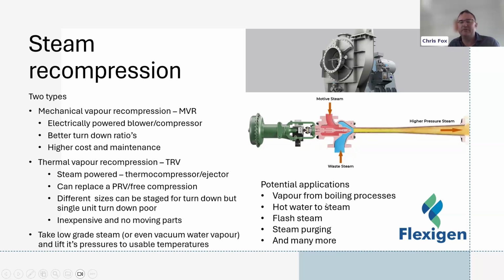Potential applications, any process where you're boiling something. I worked at the Tui's Brewery for quite a while when I was a young engineer. We had a big mechanical vapor recompressor on the kettles there. They were just boiling beer at atmospheric pressure. We took all that waste steam, put it through a 375 kilowatt Roots type blower. And once the kettle was boiling, that blower was compressing the atmospheric steam to a high enough pressure and temperature to actually maintain the boil of the kettle. So as soon as the kettle started boiling, the steam supply was switched off and it was run electrically. And it had a COP of maybe 11 or 12. Some pretty big COP. Also hot water to steam, flash steam, steam purging, and a lot more.